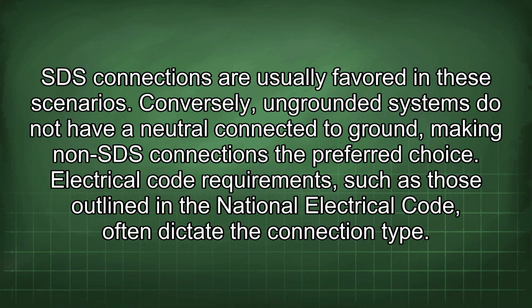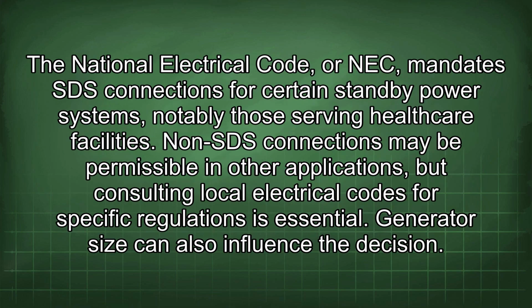Electrical code requirements, such as those outlined in the National Electrical Code, often dictate the connection type. The National Electrical Code, or NEC, mandates SDS connections for certain standby power systems, notably those serving healthcare facilities. Non-SDS connections may be permissible in other applications, but consulting local electrical codes for specific regulations is essential.